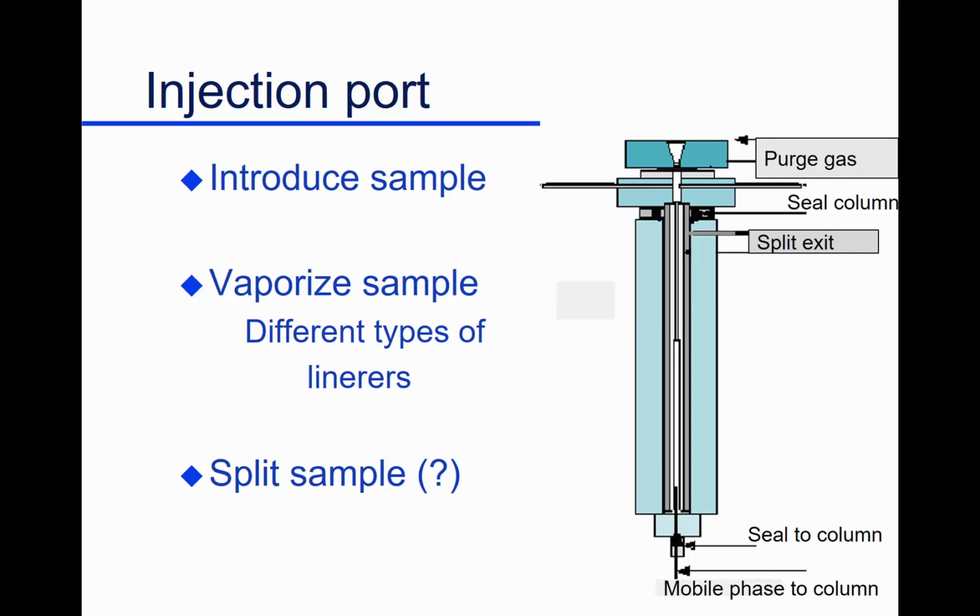Also, this is a tiny column. There isn't much stationary phase. If I put much material in that, I flood it. I swamp the whole thing, and my separation ends up being very poor. So I'm decreasing the amount I'm injecting. I'm keeping it clean by having a high flow through. Most of it gets dumped. So that's what we call a split injection. We make our sample, we split it, and only a portion gets analyzed.